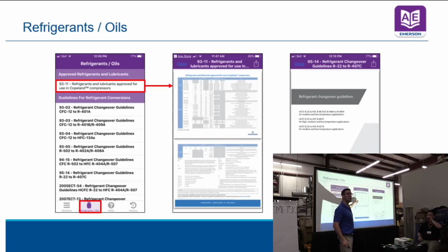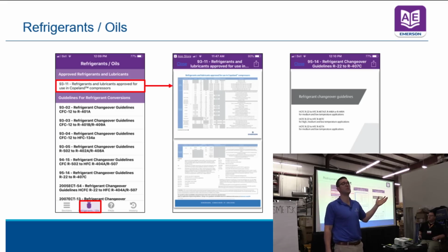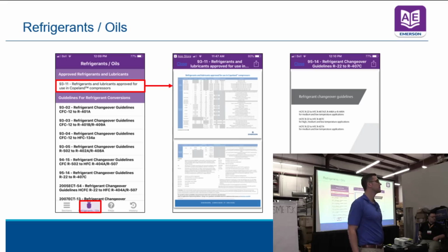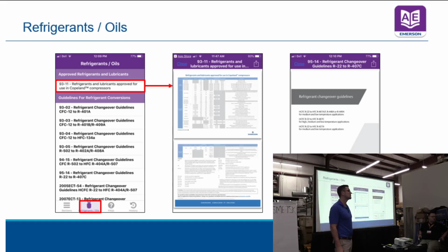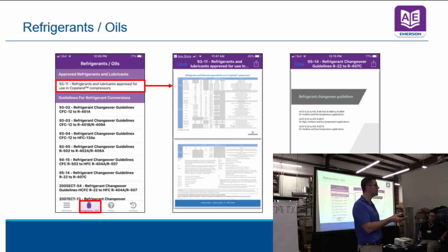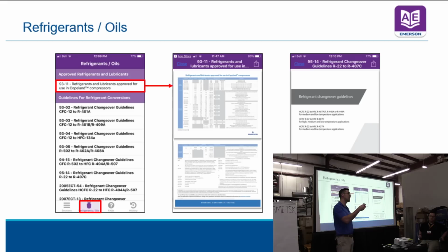Well, you really should know what kind of refrigerant's allowed in our compressors, and what kind of oils. Go check that out. We get it all the time: can we put this different oil in? Can I put this refrigerant? It hasn't been tested. Will it work? It might work, but you're not going to get warranty on that compressor. Even though it's labeled 410A on the compressor, you may be able to put something else in it, is what you're saying. Potentially. 410A is for ZP compressors only, but some of our other models, like our ZF compressors, can do multiple refrigerants.